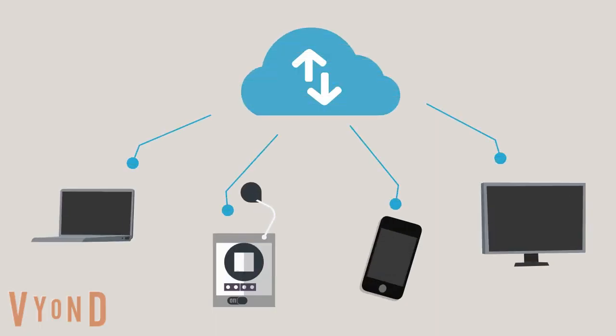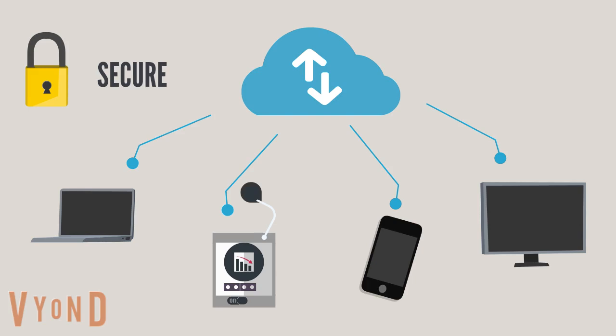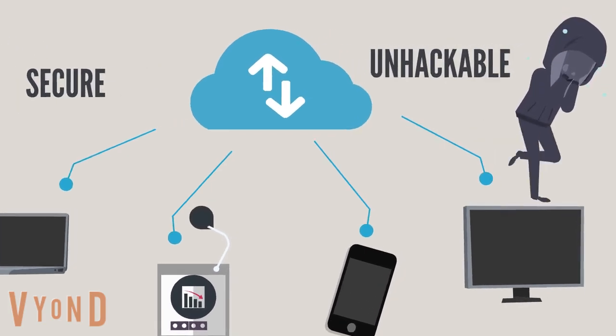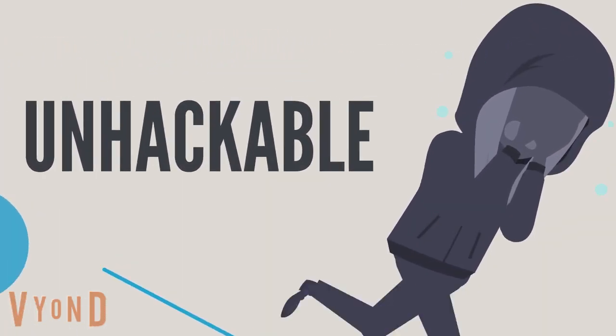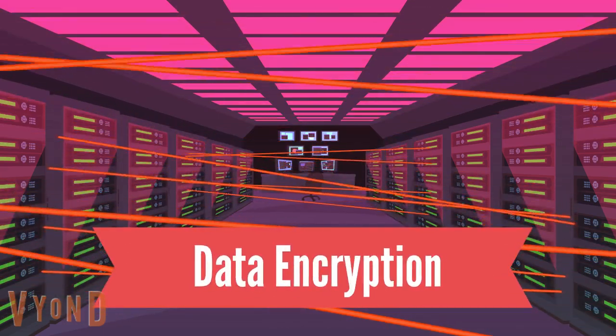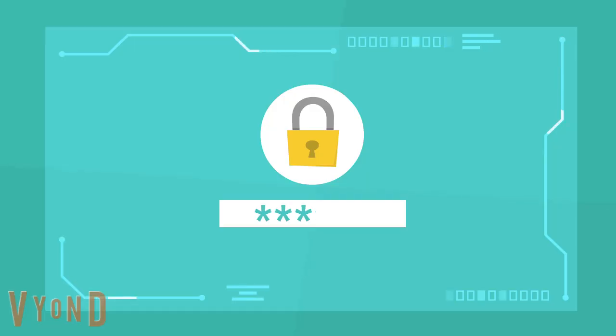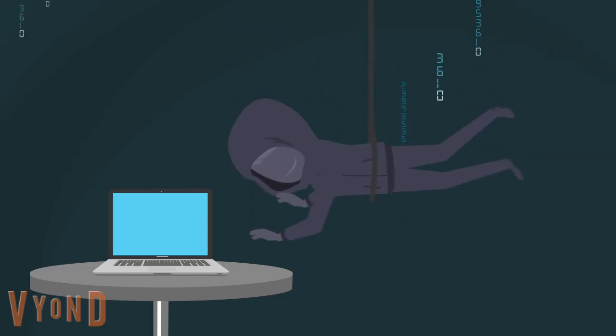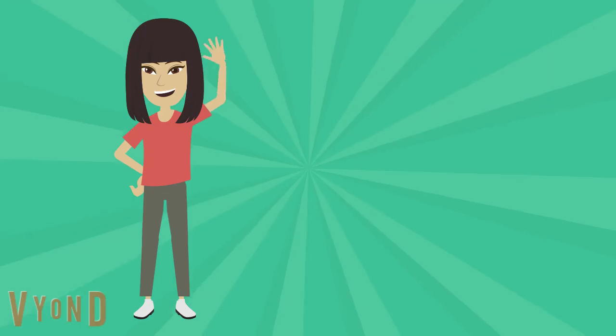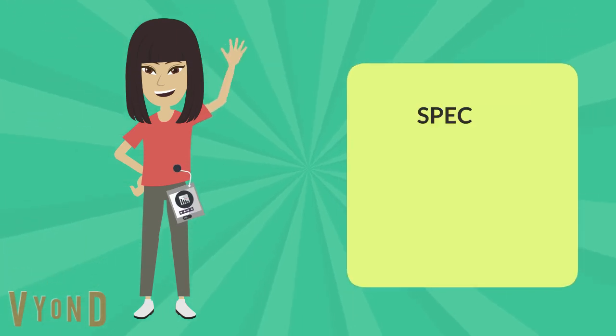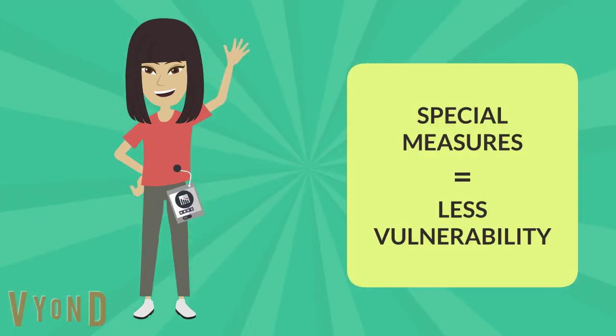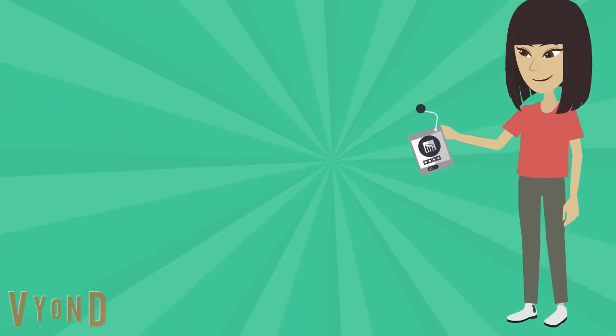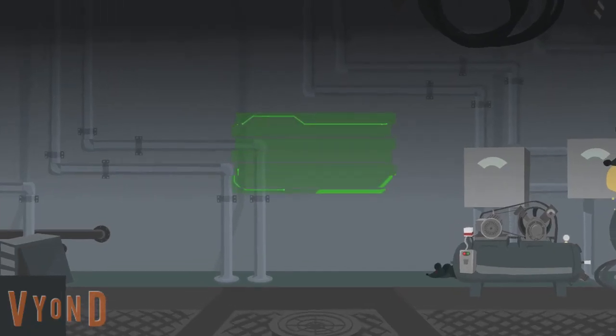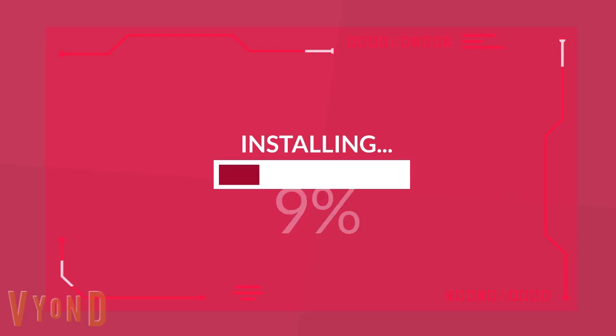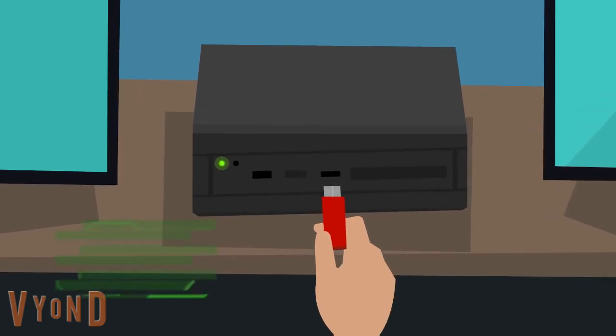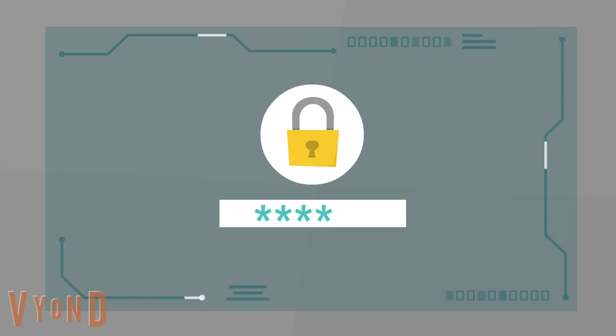Moreover, newer generation pumps do not have wireless connection vulnerability, to avoid hackers being able to remotely change the dose of insulin administered. Devices now also store sensitive data encrypted, which can only be decrypted with a password, to ensure that there is no threat to the data being accessed by unauthorized parties. Patients are also advised to take special measures to safeguard the device from hackers, like keeping their pump in their control, not sharing the device's serial number, not connecting to third-party devices or unsecured networks, not installing or using unauthorized software, and keeping the software up to date as well as their password secure.